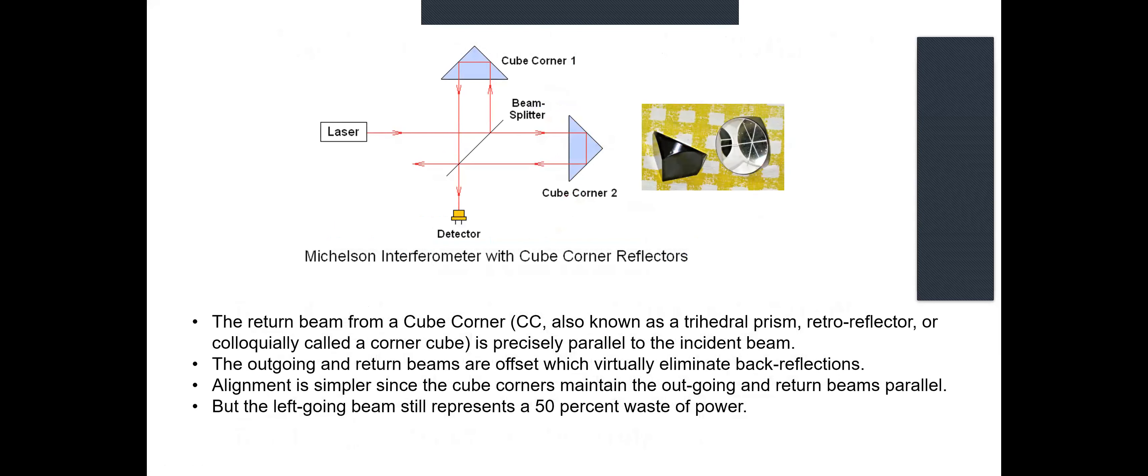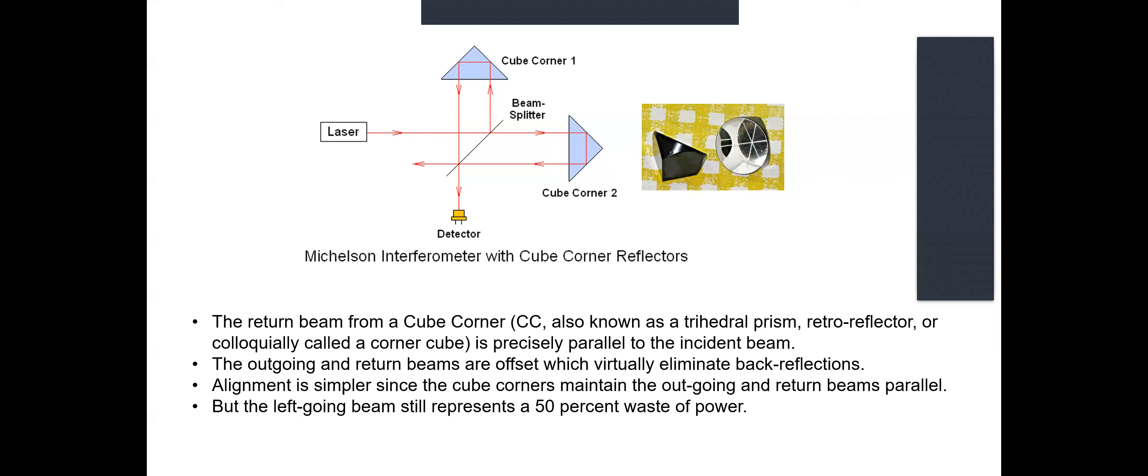So the first improvement is to replace the simple mirrors with what are called cube corners or retro-reflectors or trihedral prisms - they're all the same thing, or colloquially called corner cubes. I just think of them as a corner of a cube cut off and used as an optical reflector. Now the return beams, reflected beams do not come back into the laser. They're offset by some arbitrary amount. But there's still a waste of power in the return beam going through the beam splitter.